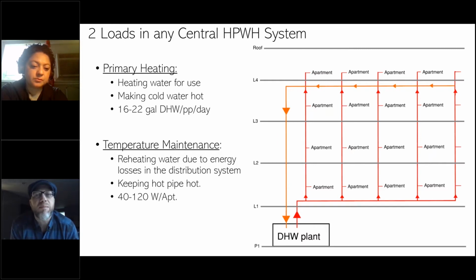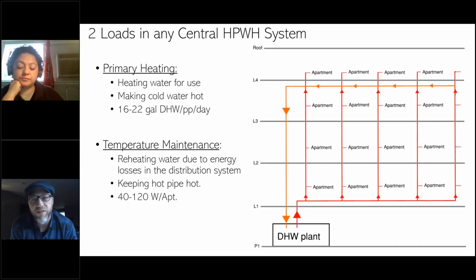This is really just to keep the line primed. It is really hard to stop the loops or to stop the recirculation pumps in these systems, so you do have to be really careful. I know there are controls in Title 24 that require us to stop these loops when there's no demand. My argument is there's always demand in these buildings. Also, when the distances get beyond about 60 feet from your plant, you can't stop the loop, or else it's going to take forever to get your hot water. So this is a really crucial piece to the total system efficiency.